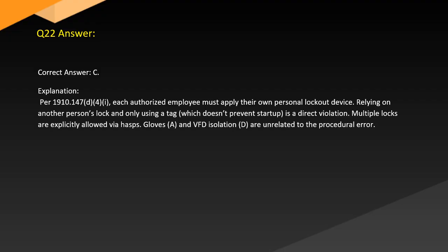Answer. Correct answer: C. See explanation. Per 1910.147 D4I, each authorized employee must apply their own personal lockout device. Relying on another person's lock and only using a tag, which doesn't prevent startup, is a direct violation. Multiple locks are explicitly allowed via hasps. Gloves, A, and VFD isolation, D, are unrelated to the procedural error.